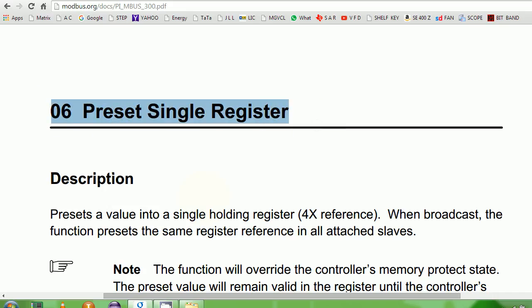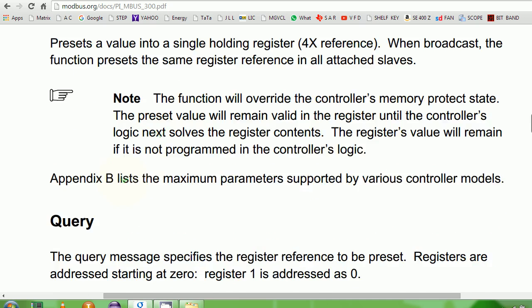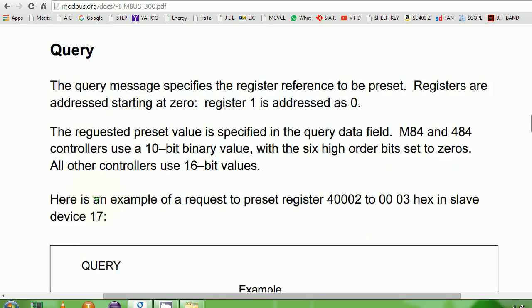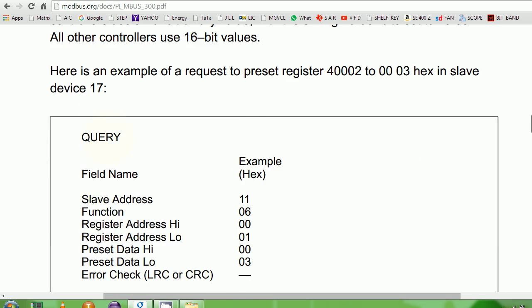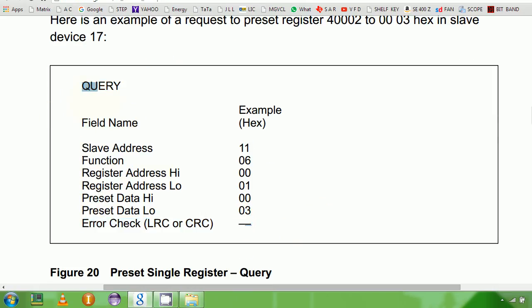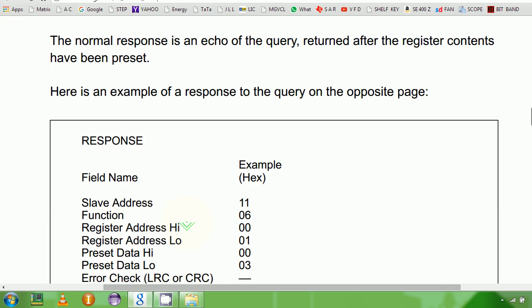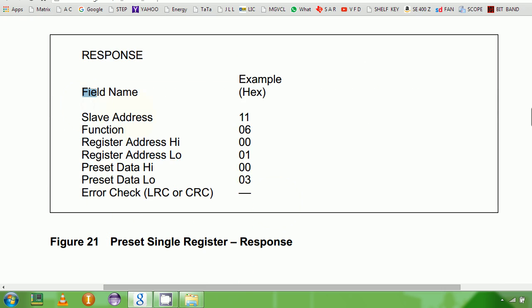Function 06 is preset single register. Preset means giving a register value. This could be any memory register, 16-bit wide, and if you're trying to write some value inside that, this is the Modbus function you're going to be using. This is the structure of the query. We'll write our electronic packet like that in terms of hex bytes and send it over serial port, and we'll expect some kind of response. This is the response which we have to decipher to know what actually happened once we throw the query to the PLC.